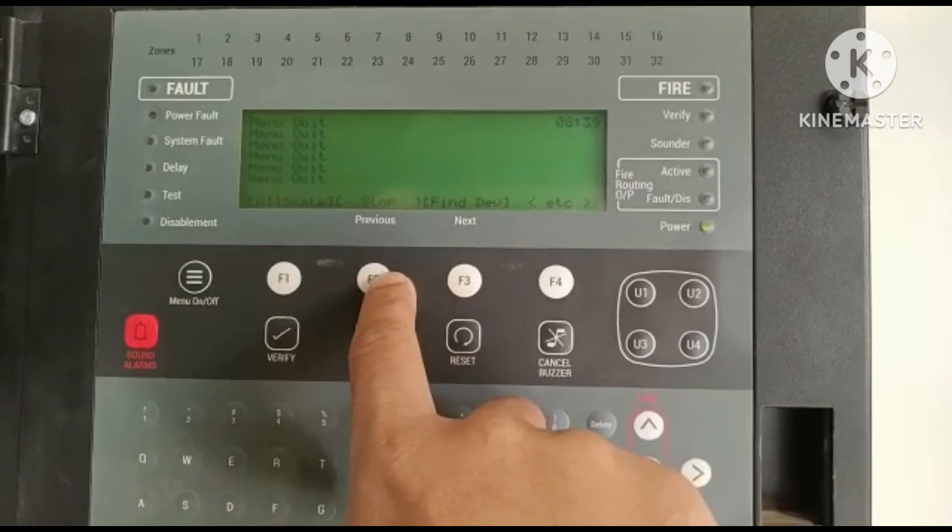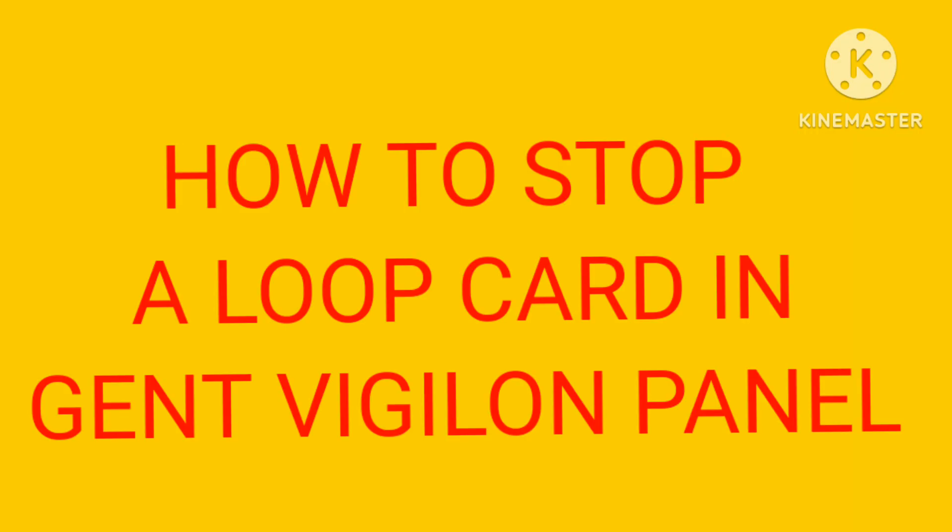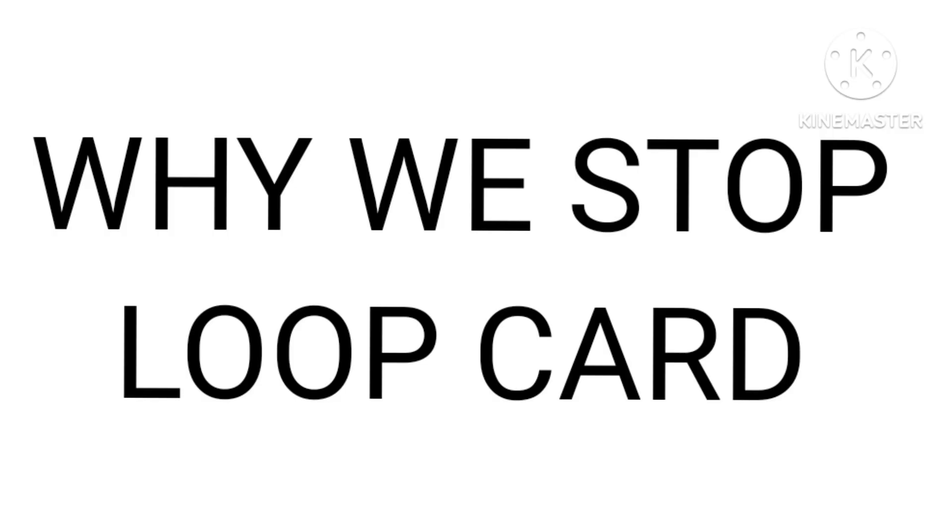Dear friends, in the Gent Vigilon panel there is an option to stop the loop card. We can stop our loop cards and loop engine in the panel. Why do we stop the loop card? Because in the general panel, the power supply unit has more cases of failure. If we turn off the power supply unit and then turn it on again, it may fail to turn on.